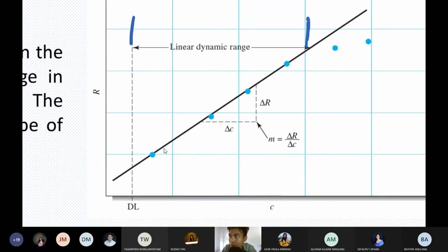So again, when establishing this curve, you must check where the linearity ends. When your data point starts to plateau, you may want to remove that part wherein the plateau starts, in order to make your linear equation.